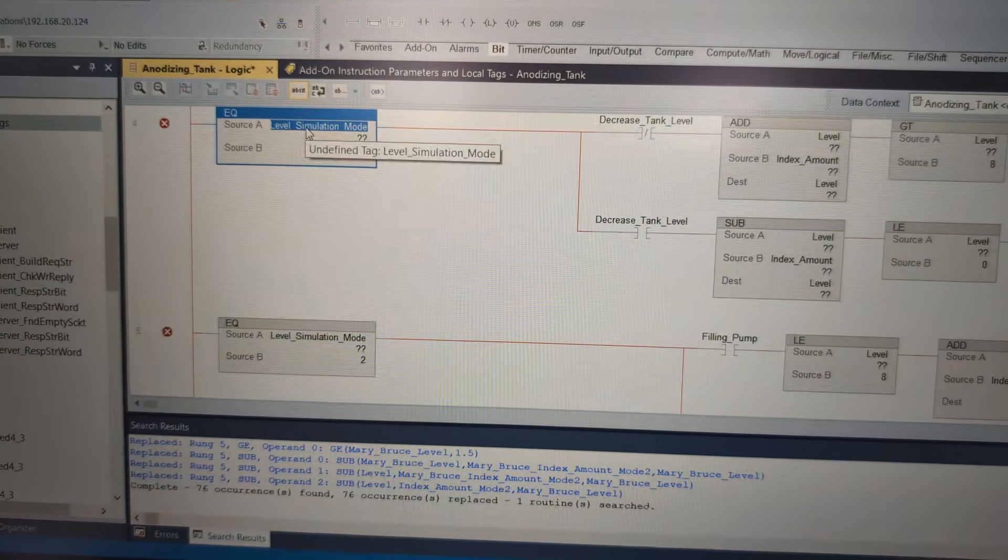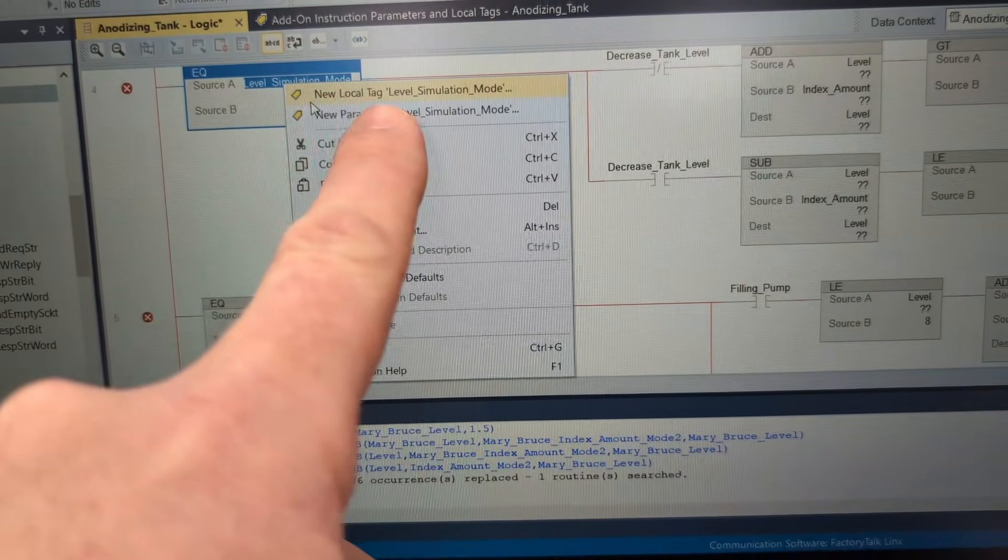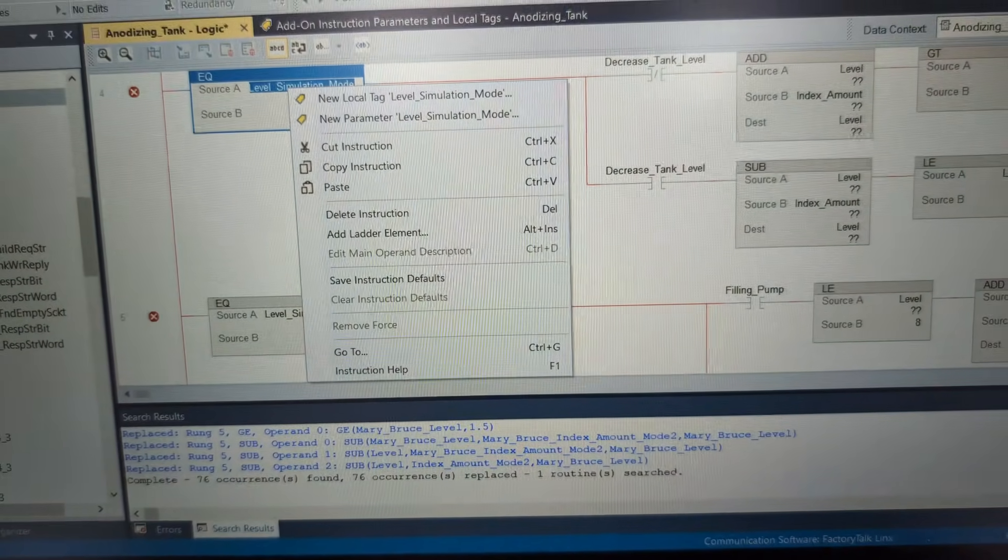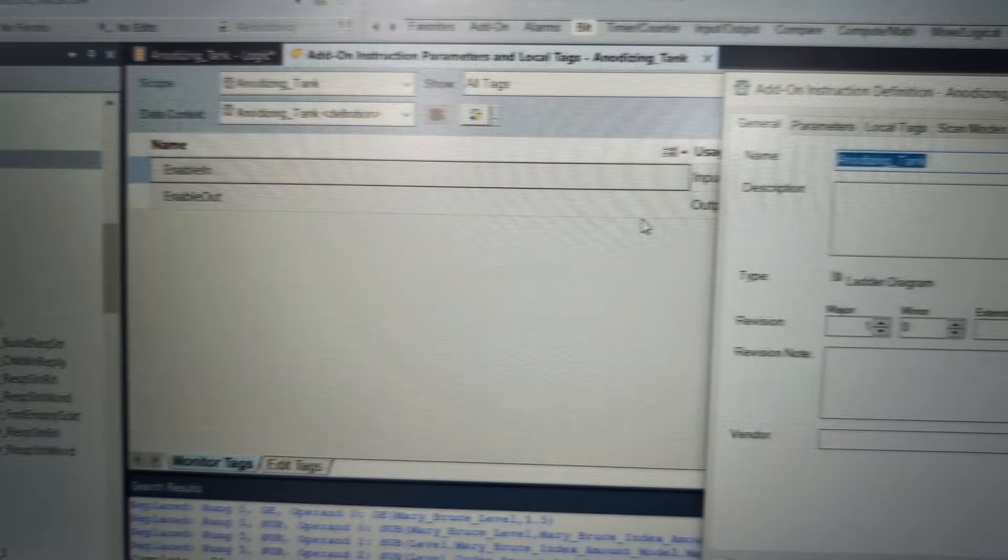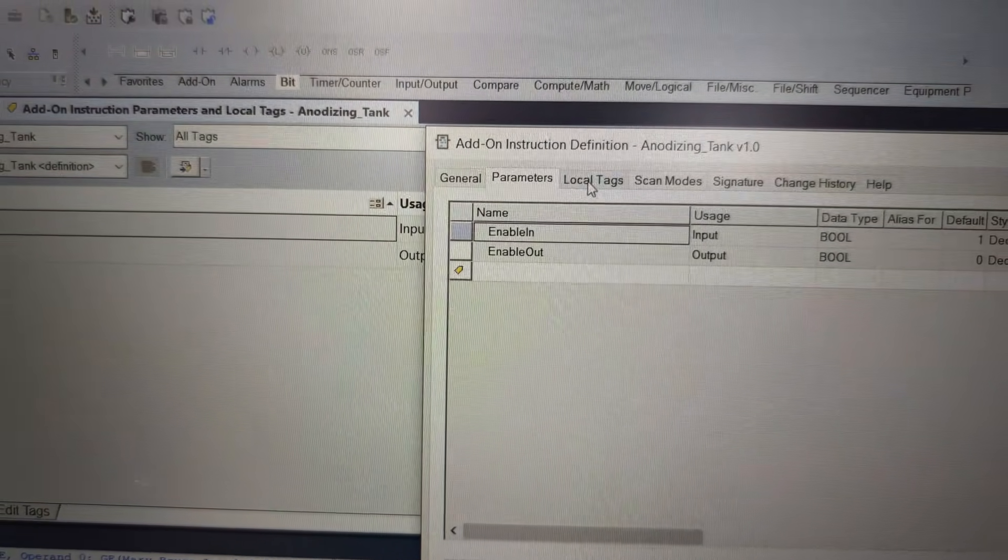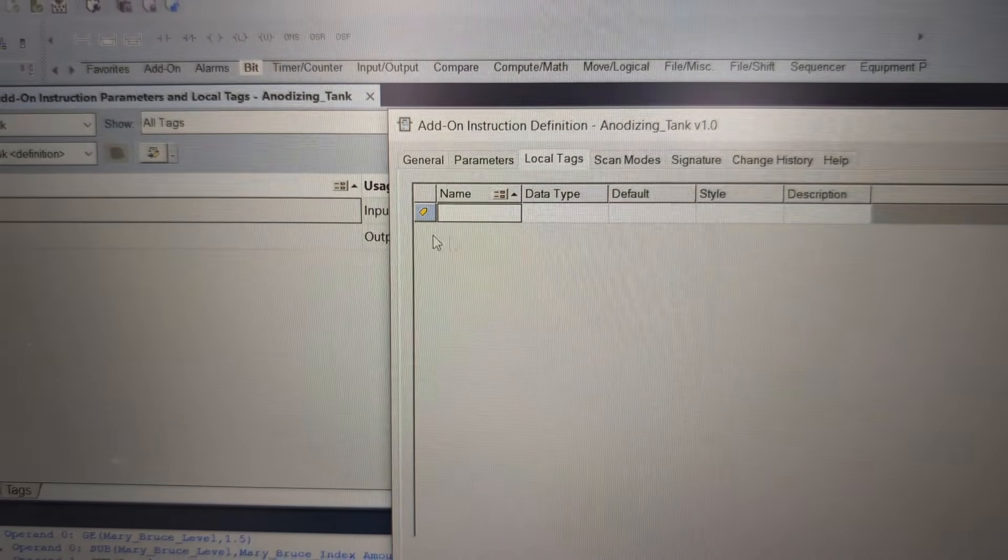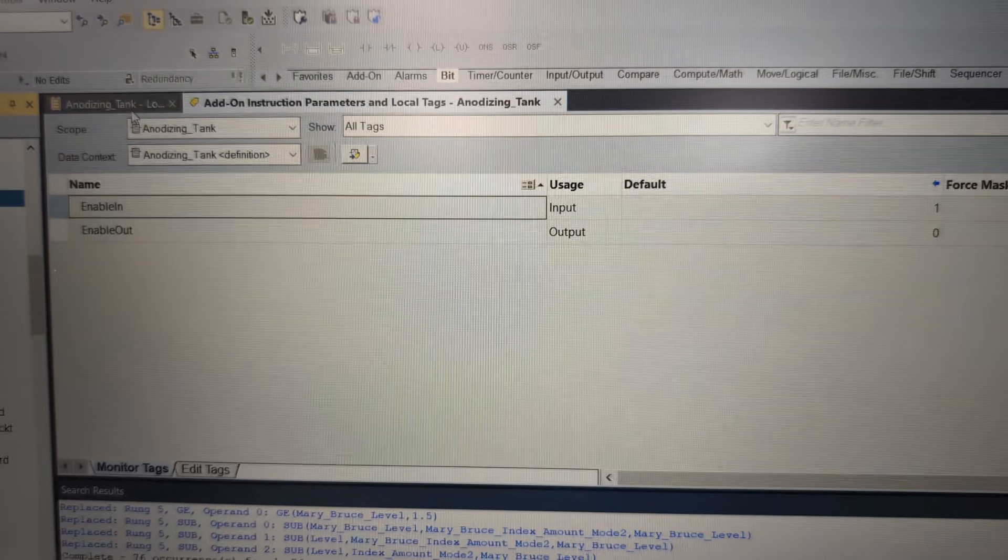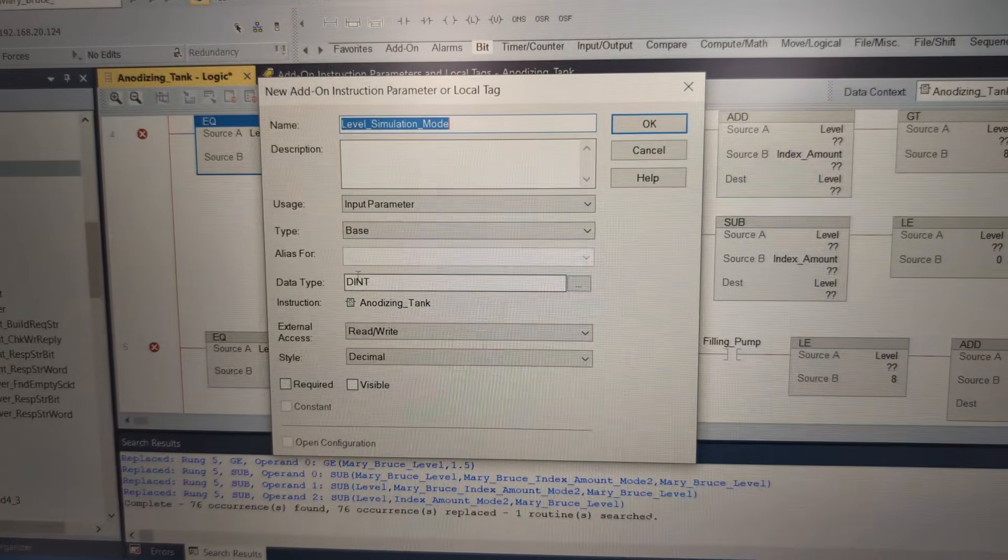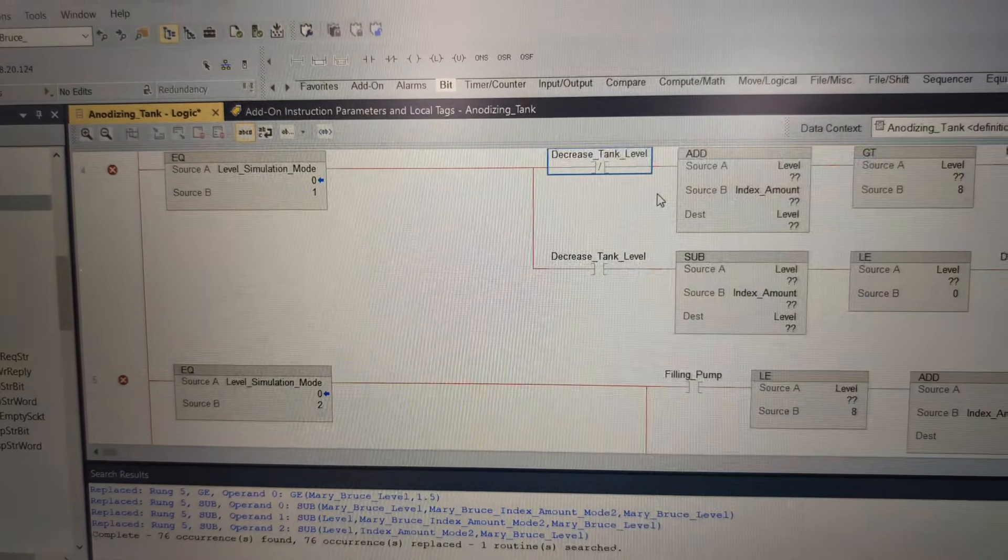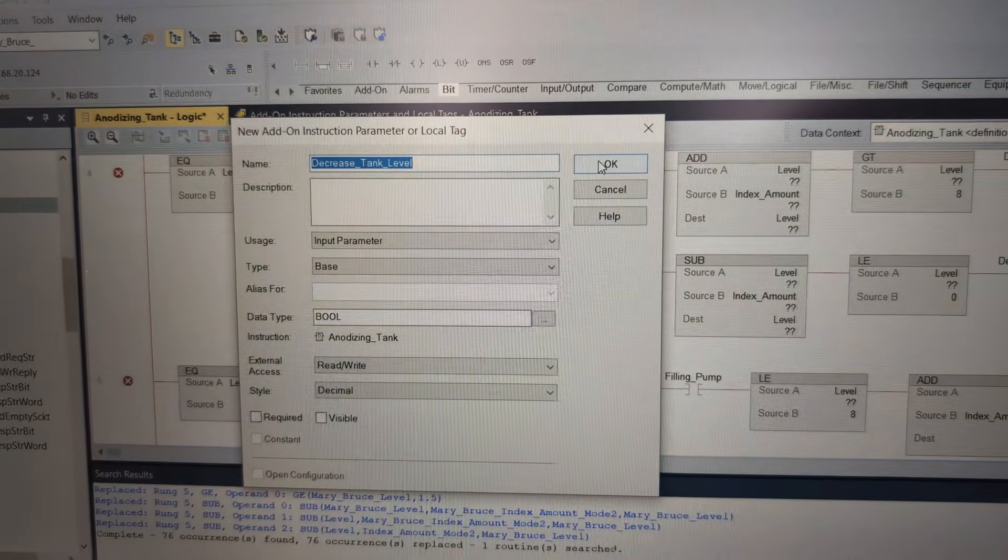We'll have all of them back open in just a second probably. Let's really take them one at a time. When we right-click, notice we could make new local tag or we could make new parameter. If we go over here and open definition, we have our parameters - these are things that you see in the Add-On Instruction. We have local tags - these are things that we use in the Add-On Instruction but they're not viewable outside of it. There's good uses for both of them but I think all of these are going to be parameters. So we're going to right-click and make a new parameter. And SimulationMode, that is a double integer, and this one right here, that will be a boolean. You don't need to watch me do all this so I'm going to hit the pause button.